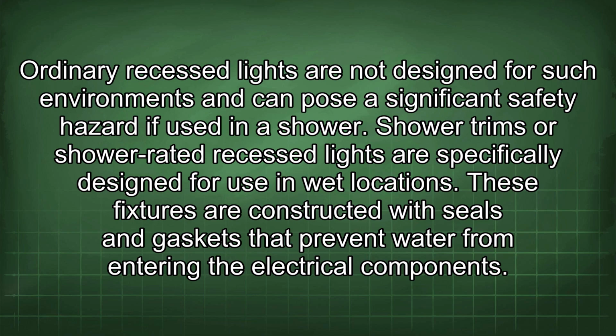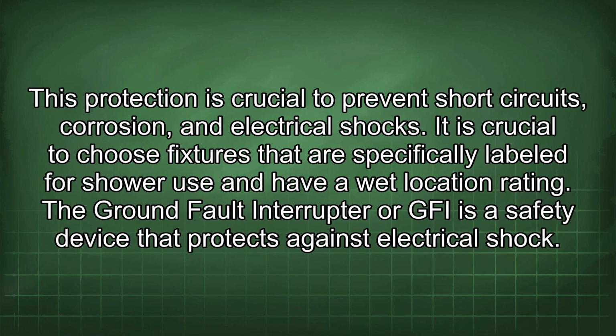Ordinary recessed lights are not designed for such environments and can pose a significant safety hazard if used in a shower. Shower trims or shower-rated recessed lights are specifically designed for use in wet locations. These fixtures are constructed with seals and gaskets that prevent water from entering the electrical components. This protection is crucial to prevent short circuits, corrosion, and electrical shocks. It is crucial to choose fixtures that are specifically labeled for shower use and have a wet location rating.